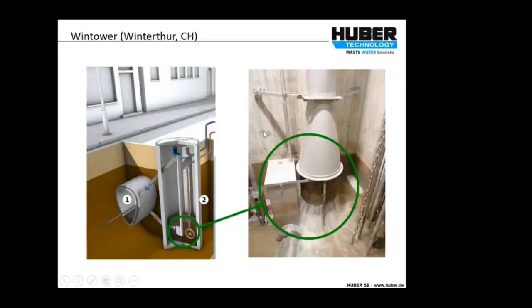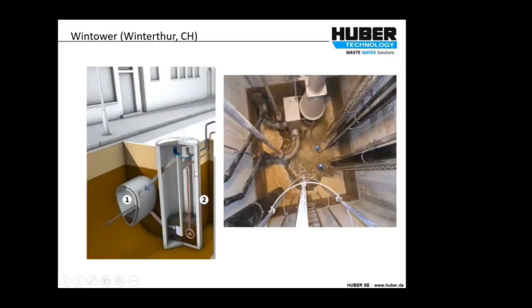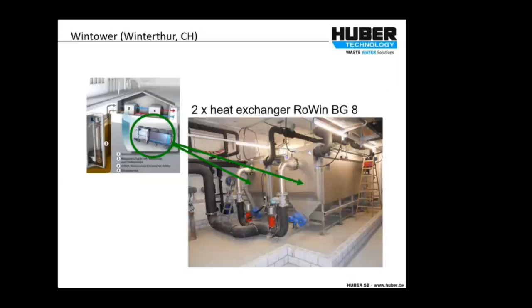That's the pump station looking down from the top, so you can see the duty standby pumps on the right hand side here, the incoming sewage pipe coming into this unit here, into the screen. The screenings will come up here, and these pumps will take the sewage out and away into, okay, it's not the next picture, actually I'll go to the next picture, into these, which are the two heat exchangers. So this is the first element of the design that I showed you there. These are two what we call BG8s. These are what's actually taking that low grade heat out of the sewage and into the internal flow mechanism for the heat exchanger and away into the heat pump.